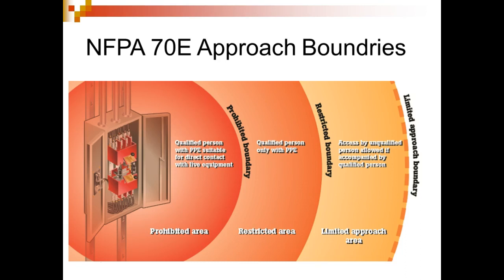This is all defined by NFPA 70E. NFPA did such a good job that a lot of this has been imported into OSHA. So there's a lot of stuff in the National Electrical Code that's in the OSHA 1910 standard, which is workplace safety. There's also a lot of stuff that's in 70E. The 70E is not law, it's recommendations. It's up to your company whether you follow 70E. Just about every major company I know of around here looks at this now because it does so well. If you do what 70E says, then as an employer, you're going to be okay.